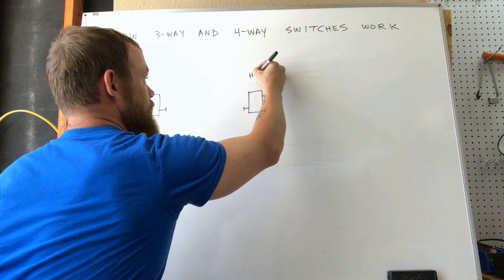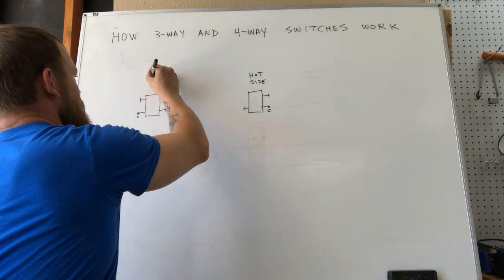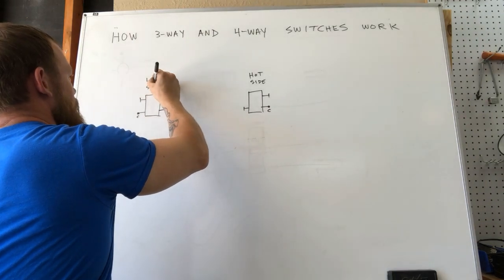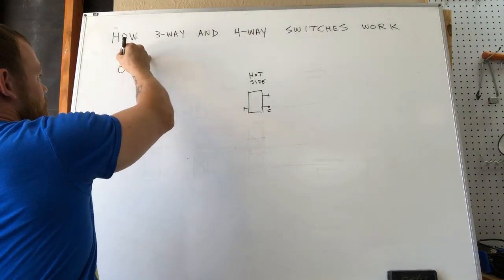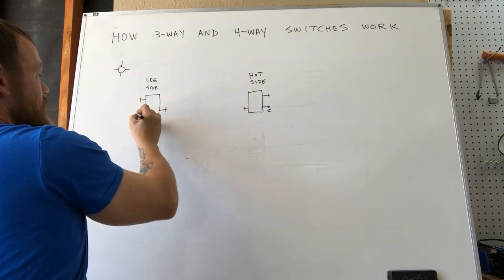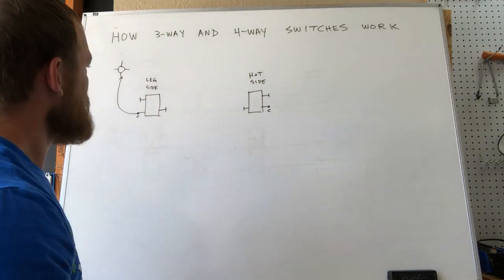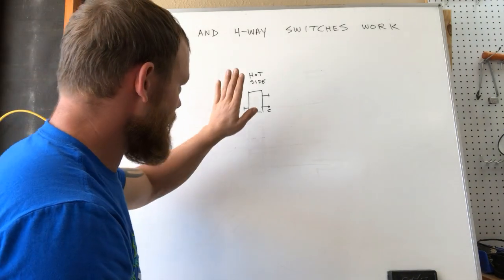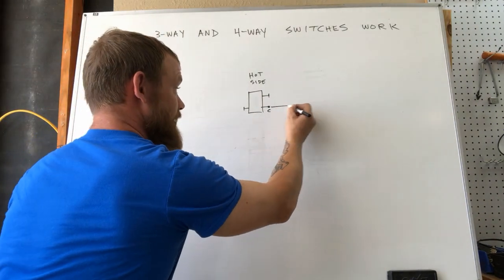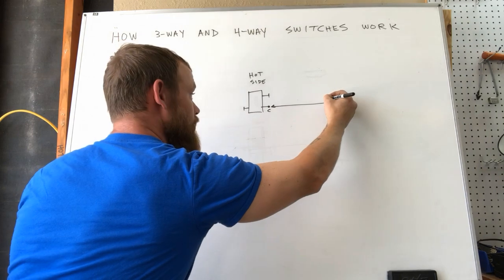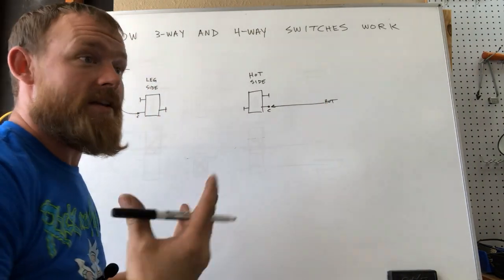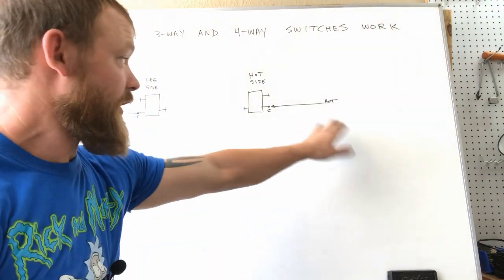So how a three-way works is we've got a hot side and we got a leg side. The leg side is where you're going to have your switch leg, which is a wire that goes from the device up to the actual light itself. Then the hot side is where your incoming hot is going to be from a panel or from another plug or whatever. That's where you're bringing the power into.